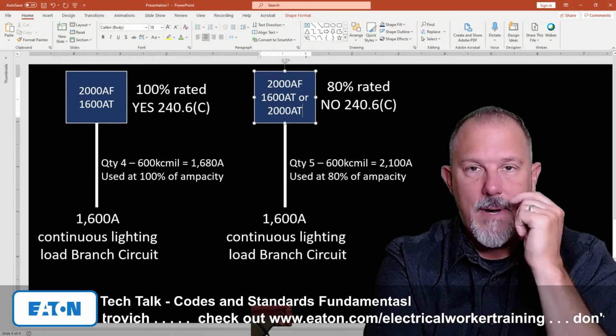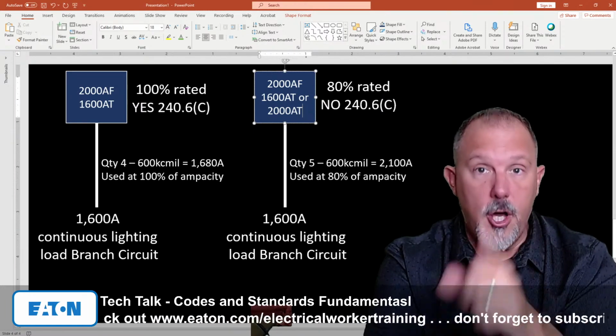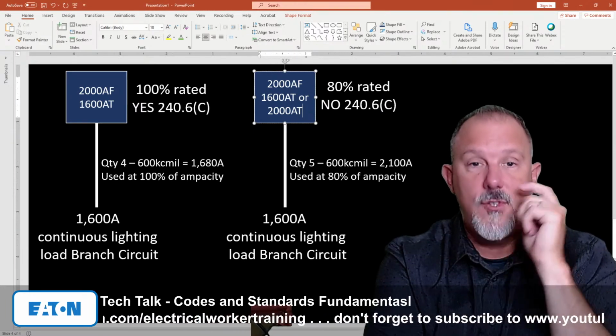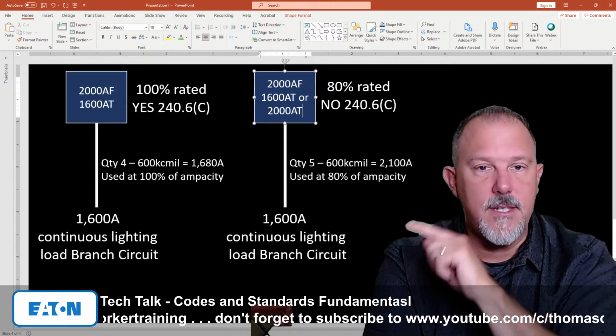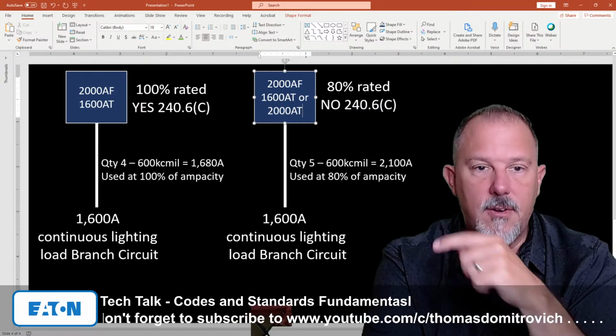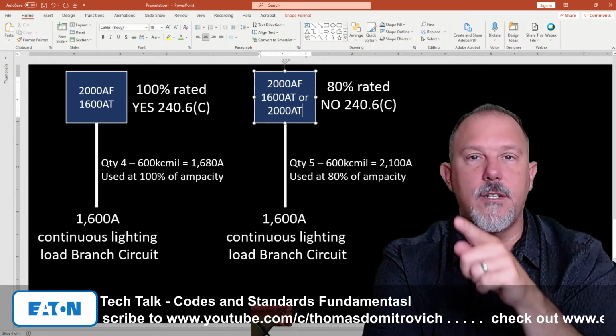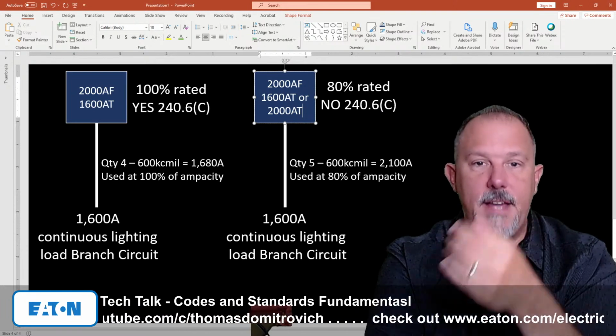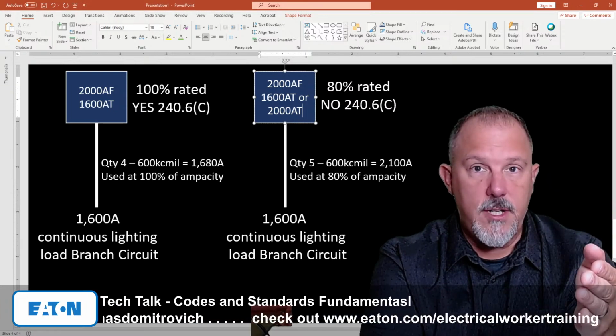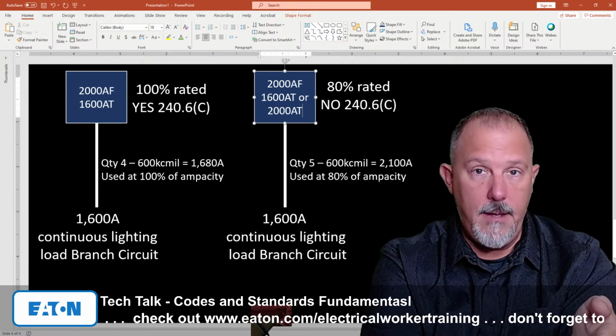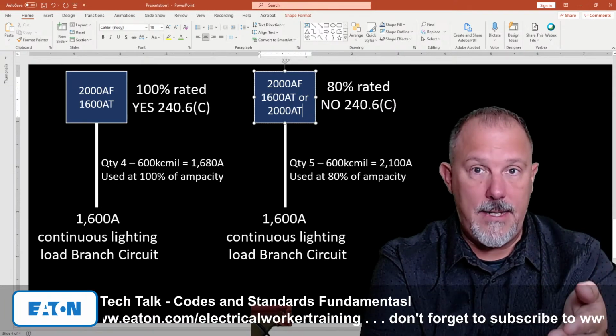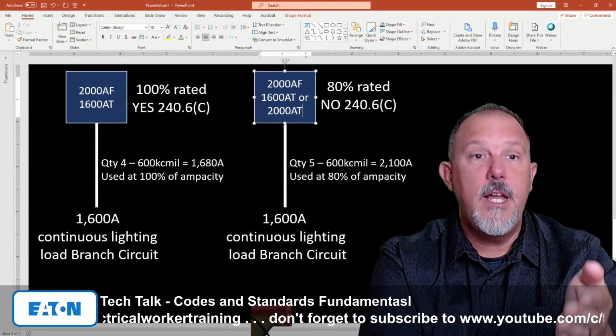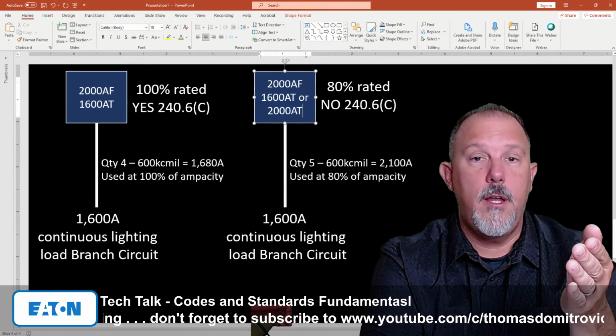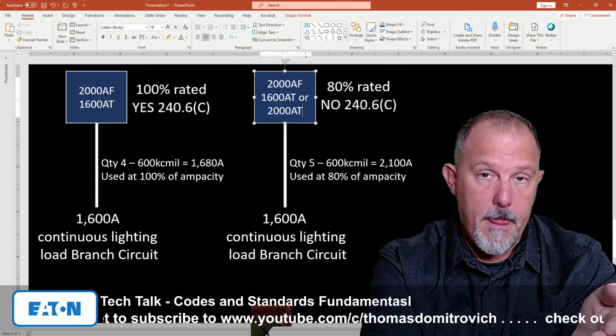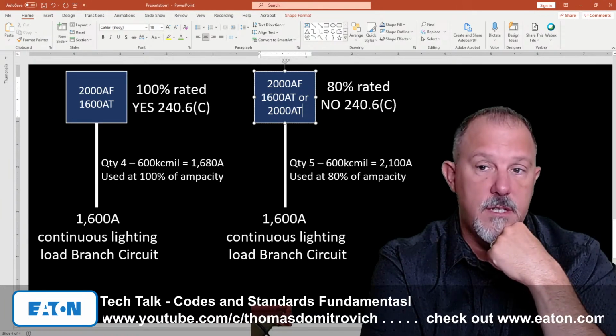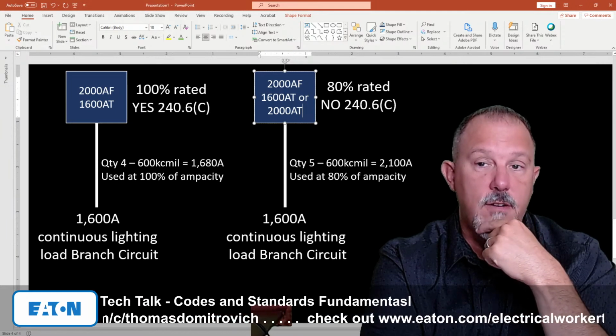So my answer to your original question was no. You cannot take a 2000 amp frame, 80% rated breaker, adjust it to 1600 amp trip, put 1600 amps worth of conductor, and use that 1600 amps worth of conductor at 100% of its ampacity. That would violate, if it's a branch circuit, 210.20a. If it was a feeder, it would violate 215.3. But on a service, you might be able to do that.